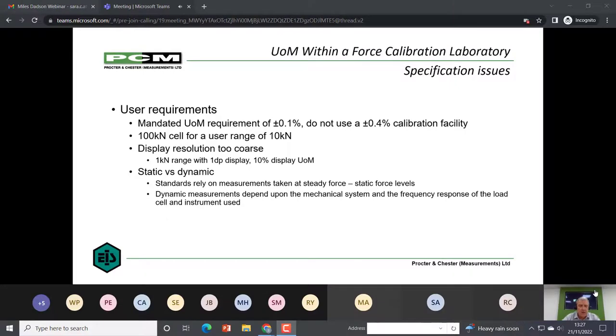So coming on very close to the end now, we see quite a lot of specification issues coming through. To give you a few of the more common ones: you have a requirement at the end of use that you have to have a calibration uncertainty of 0.1%, where you wouldn't use a calibration facility of 0.4%. You wouldn't use a 100 kilonewton cell for a 10 kilonewton range. A very coarse description of that would be, you wouldn't use bathroom scales in the kitchen for baking ingredients. It would be a pretty horrific cake.